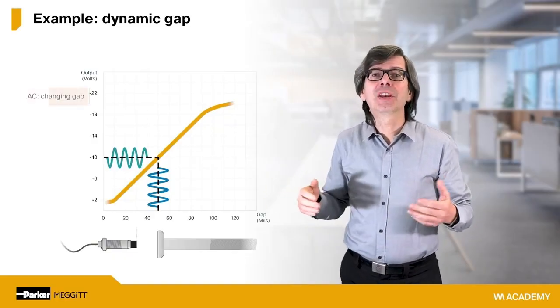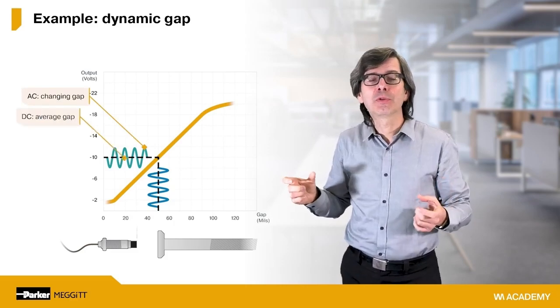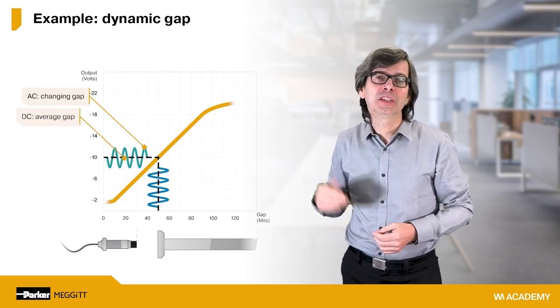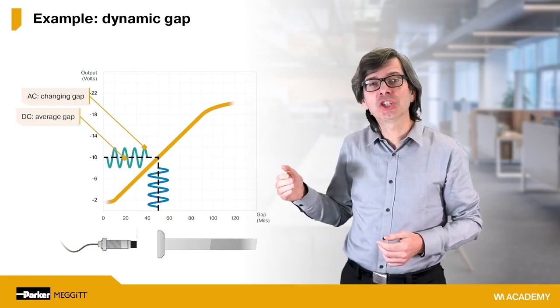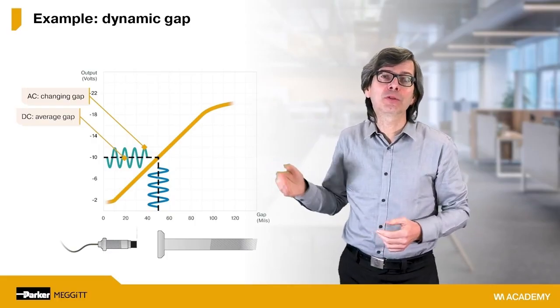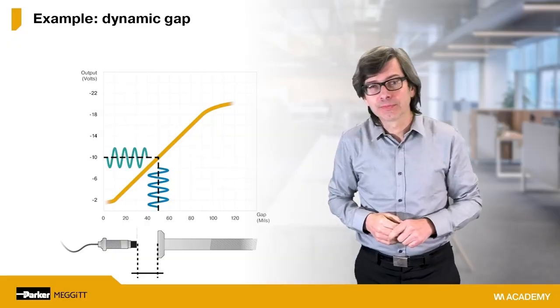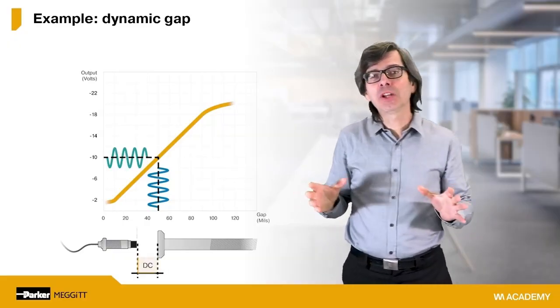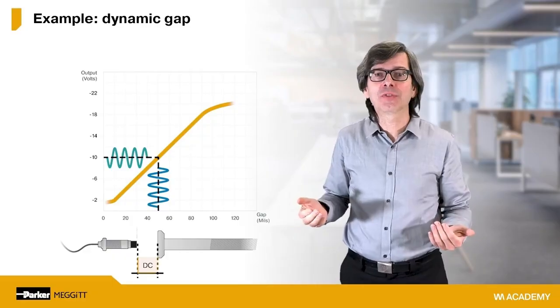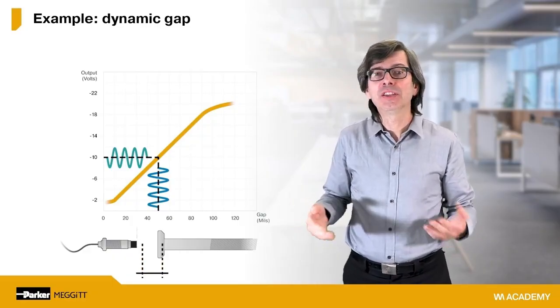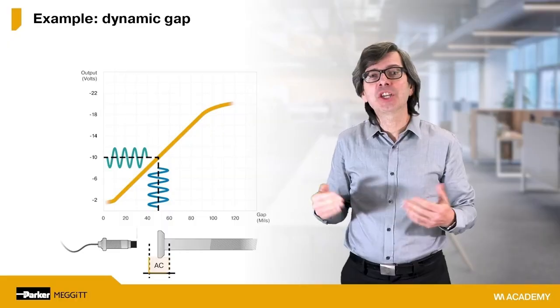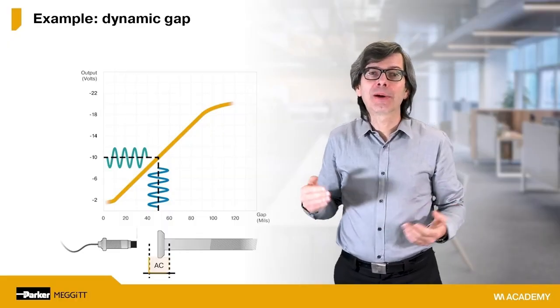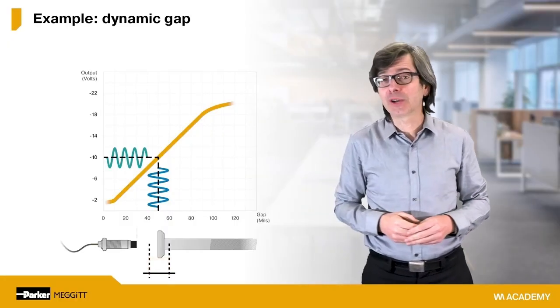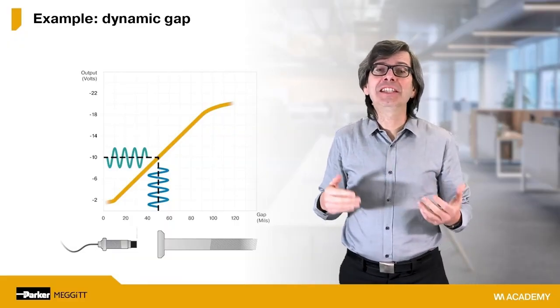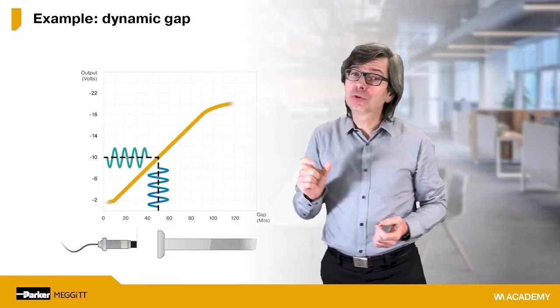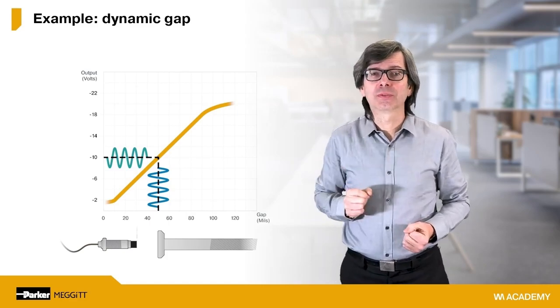A real probe will exhibit a signal with both AC and DC components. The AC component will reflect the changing gap, while the DC component will reflect the average gap. Physically, the DC component represents the average distance of the shaft from the probe. The AC component represents how the shaft oscillates about its average position as it vibrates. The amplitude of this AC component should not be confused with the DC gap voltage.